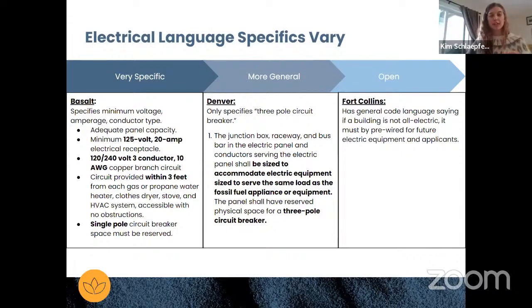So to clarify, you're saying if future electrification capacity would kick it up to 3 transformers, would you still provide the physical space for that transformer? Or is that where you'd back off and say we don't want the space if we don't know things will electrify? Yeah, or if there's future flexibility in what you can provide—if you could change out the transformer to a higher capacity and avoid the need for a third or second, from a space point of view in a condensed urban setting, that's going to be preferable.